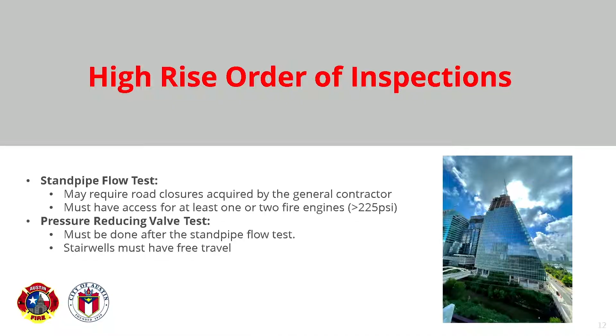Once we get the standpipe flow test done, we can test all your pressure-reducing valves. The main requirement for that is we need to be able to get up and down the stairwells. If there's scaffolding all throughout the stairwells, I'm not going to schedule it because it's not time appropriate - it's going to take far too long to work around all the scaffolding to try to get to your PRVs.